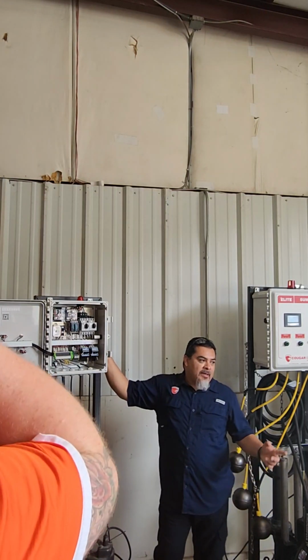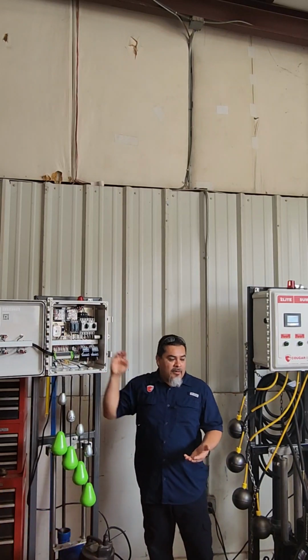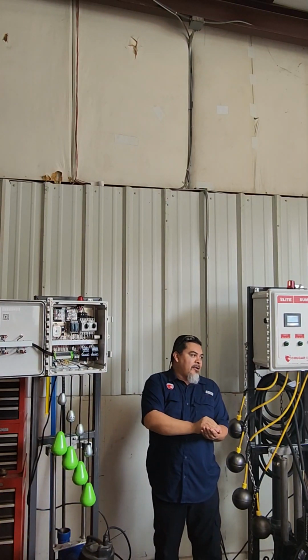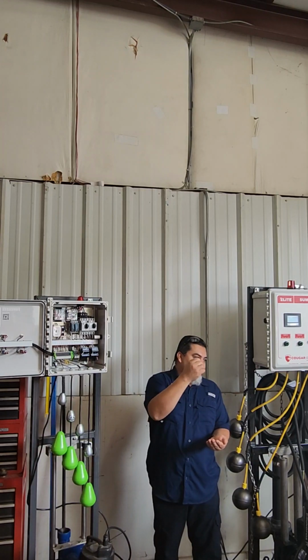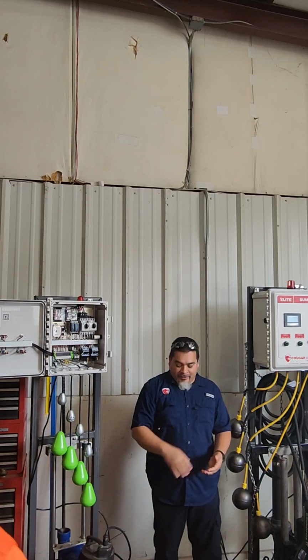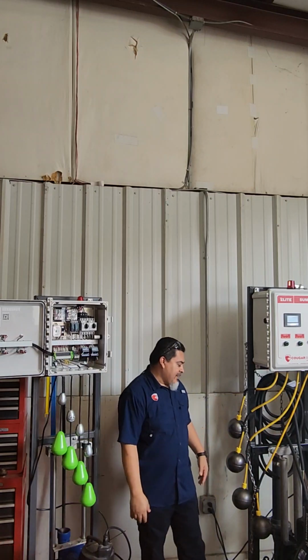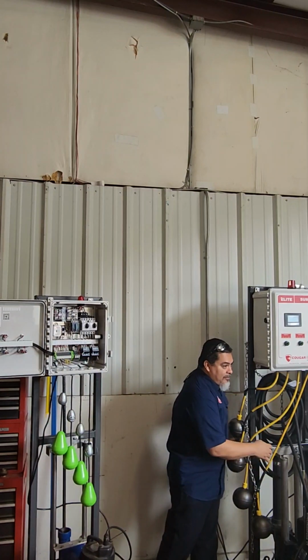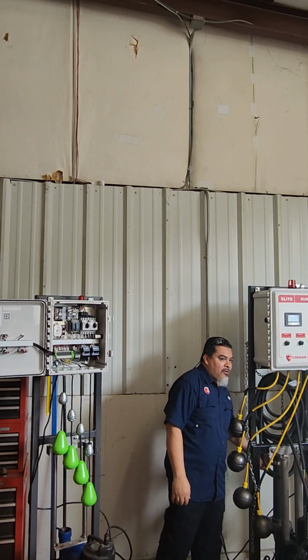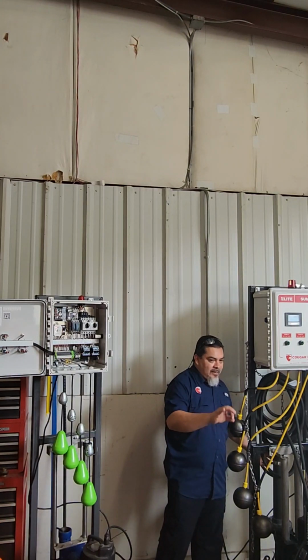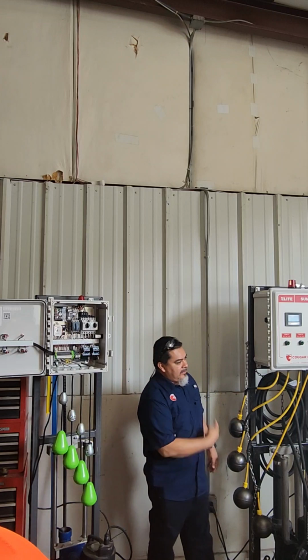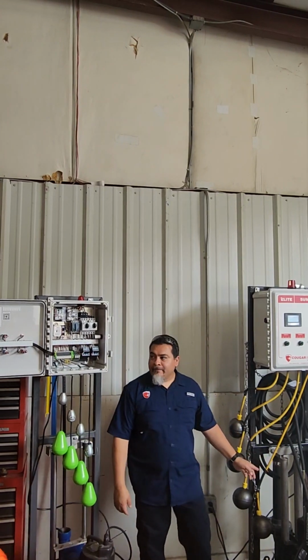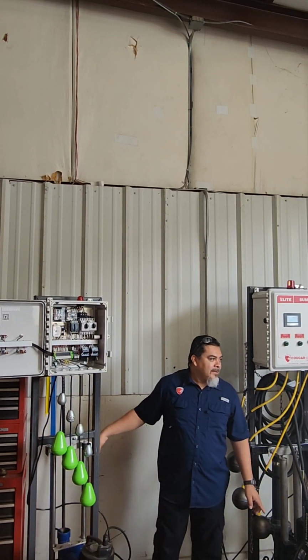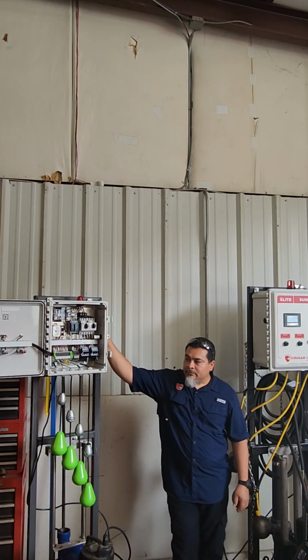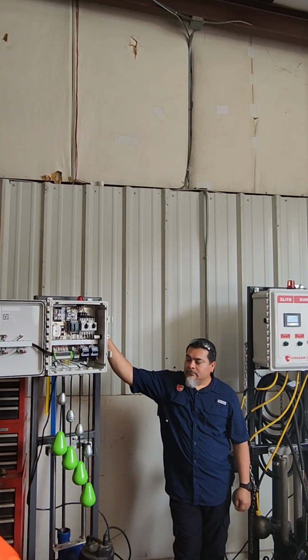And that's the other thing. If you set it back in there with water in there, you're going to pull an air gap in between, like flipping a glass of water and putting it inside. You can have that air. So I always recommend, hey, you can just pull it up, let it breathe, and set it down, or just drill a little hole on the back of the pipe, like a 1/4 inch or whatever. A bleeder. Gotta be below the check valve. Gotta be below the check valve. That's fine, especially if it's a pit, like a loading dock or something like that, where it can go dry. It's good to have one there so the next time the water comes up, it doesn't catch that bubble there.